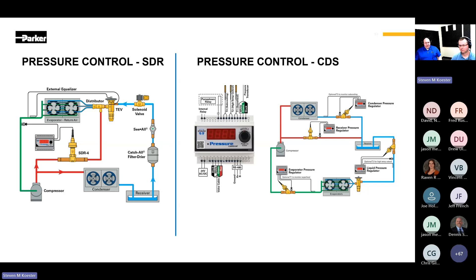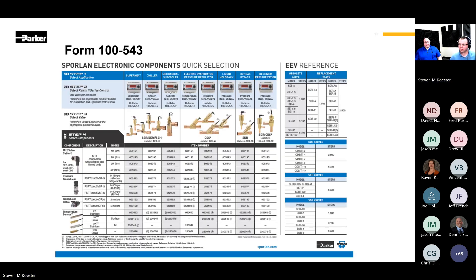The pressure control SDR schematic: on the left, we have a pressure control paired with an SDR. This is one variation of what a hot gas bypass system can look like. The SDR valve regulates off the suction pressure. More information about the additional components and applications for each controller can be found in Form 100-543 on Sporlan.com.